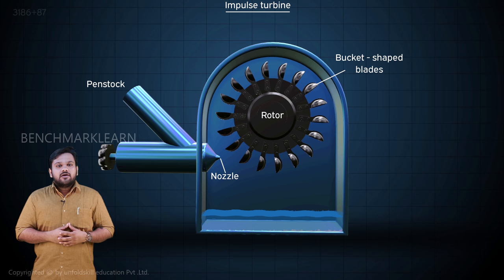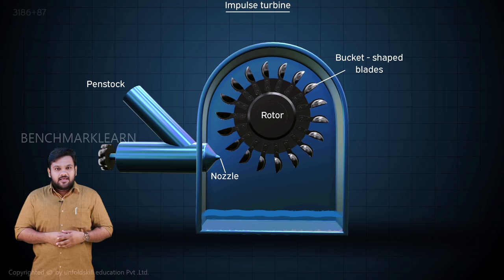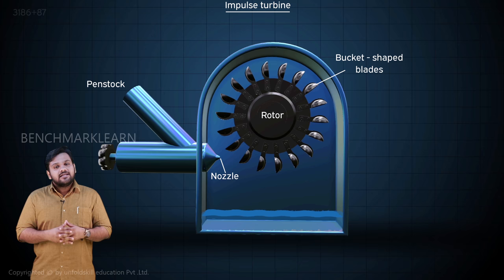The nozzle is attached to a penstock, a pipe which extends all the way up to the water reservoir, which is usually located several meters high. This water has potential energy due to its high location with respect to the nozzle. This is converted to kinetic energy, and hence a high velocity water jet comes out of the nozzle. Inside the nozzle there is a spear-like arrangement which can be loosened and tightened to control the flow rate of water.